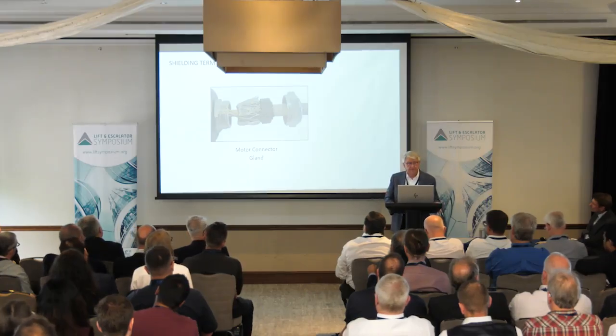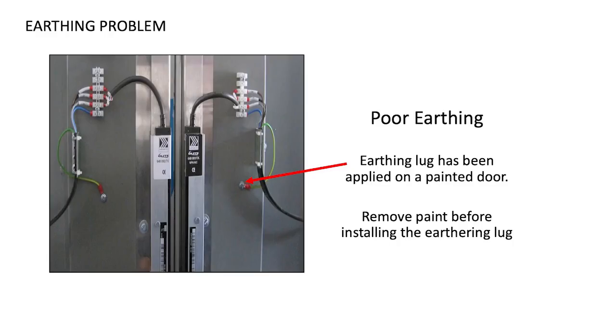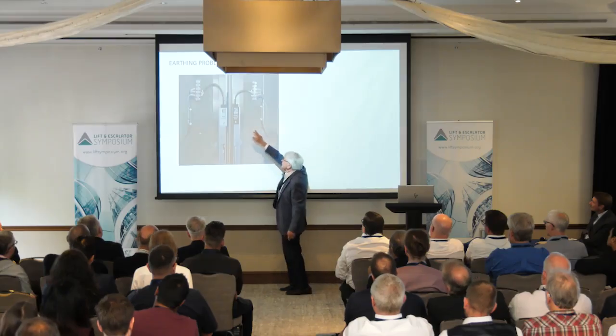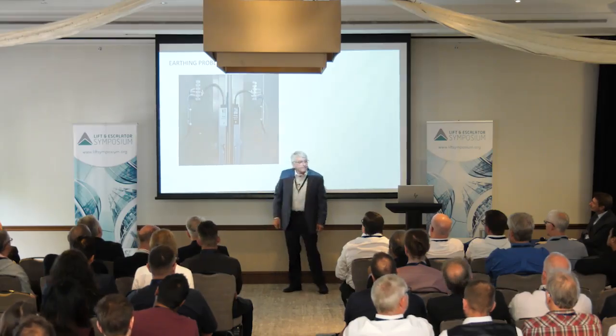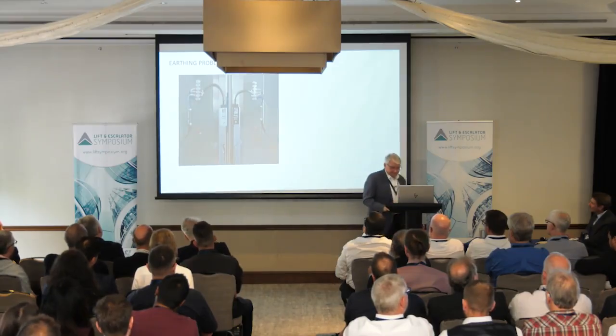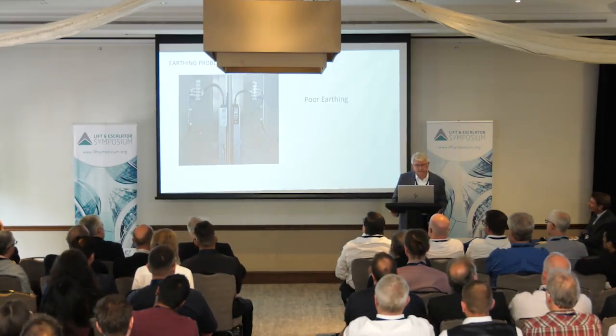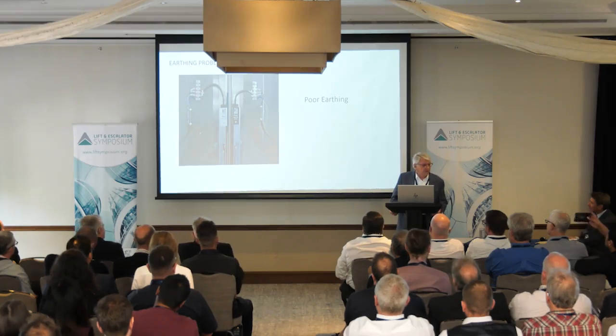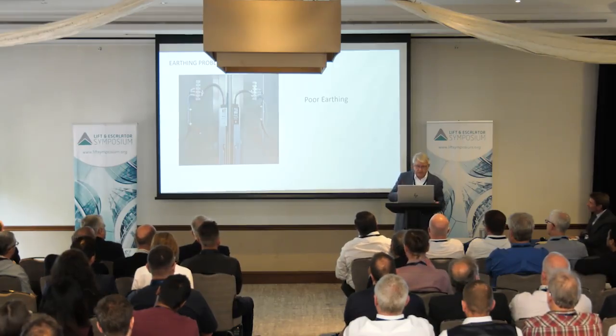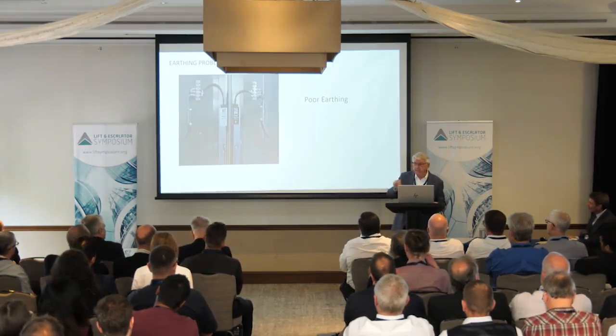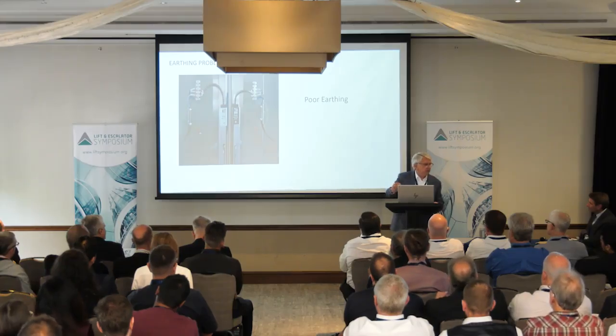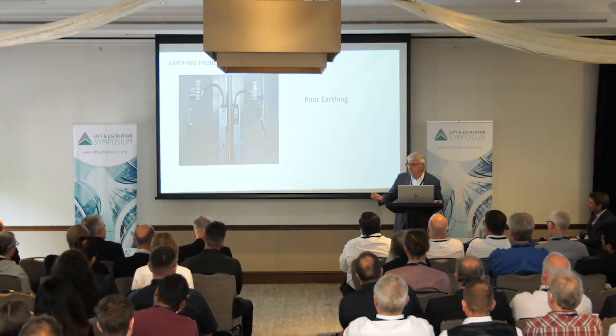Now I'm going to show you some samples of things that weren't quite right. And this looks like it's very well wired. These are photos of light curtains. And what you have is the green and yellow earthing conductor, and it goes right here and it's screwed into the door. Okay, it looks like it should work well, except they didn't scrape the paint off the door. And so now you have good continuity, but you don't have good contact for radio frequency. So you have to take some sandpaper or something and scratch all the paint off, and then put the ring lug on, and then tighten it up, and then you have a good solid earthing.